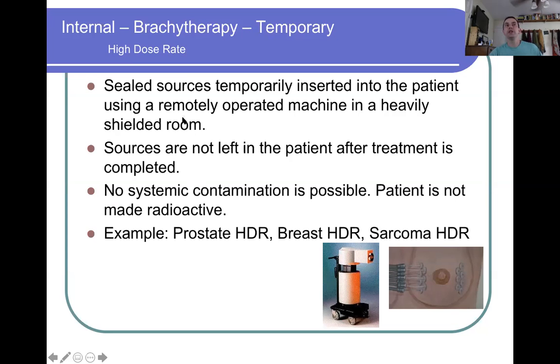These are very short procedures. Because of the high dose rates, they use what we call a remote afterloader, because you would not want to be a physician handling the source yourself. It's generally like a 10 curie source, so that's a very, very high activity. These procedures need to be done in very heavily shielded rooms. Anytime we have a source replacement for these, we have to take a survey, similar to how we would handle a replacement LINAC. It's a little less extensive of a survey, but you still have to treat it seriously, because the shielding is providing radiation reduction to the areas surrounding the HDR vault that is commonly used.